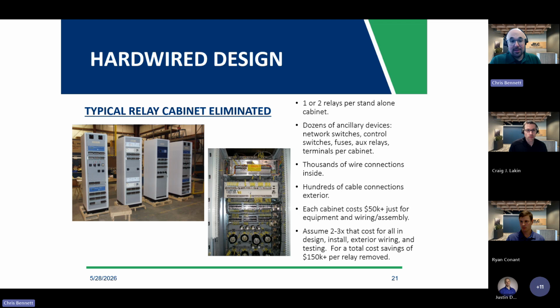The hardwire design, this is what we typically see nowadays in most control enclosures. The racks that we reference are in the picture on the left. At least one, if not two, of those racks per relay zone of protection. On that rack are also many other devices such as switches, fuses, aux relays, handles, you name it. Everything that takes up space costs money, has long lead times in some cases.